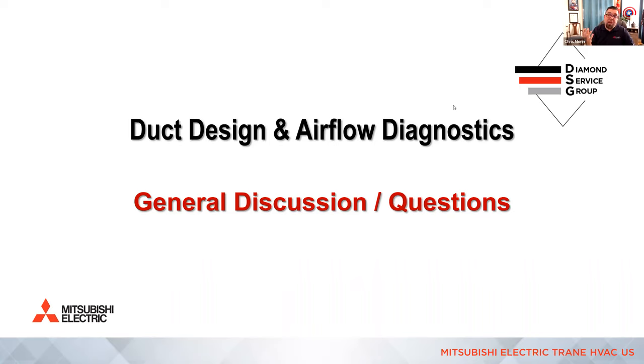Obviously, with less volume of air, you've got to check those registers. I'm willing to bet they're only going to throw a certain distance because they were sized for the furnace. So with lower volume of air, there's lower velocity, and you need to make sure you communicate that to the homeowner. Like, look, it's going to feel like it's barely blowing. That's because it's part load and it runs at a lower volume of air. If you want me to redesign this entire system with a new furnace, we could, but it's going to cost a lot more. Hopefully that makes sense to you, Tom.